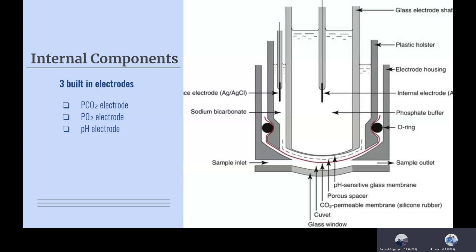and that's the PCO2, PaO2, and the pH sensors. Those three are the only ones that are directly measured from a sample of blood. The other values that we get are calculated based on the other numbers.